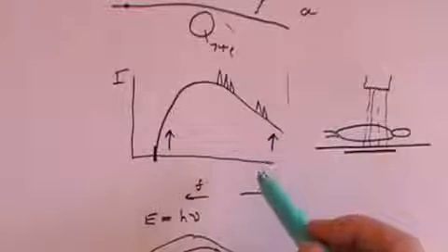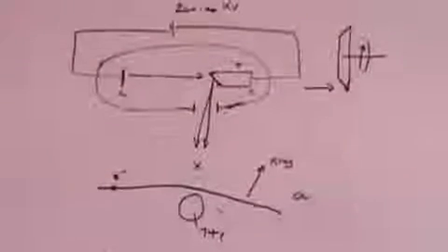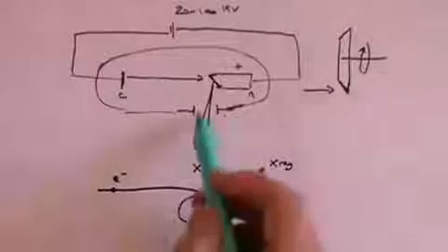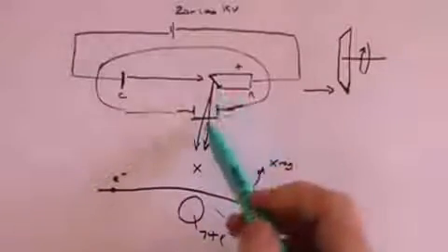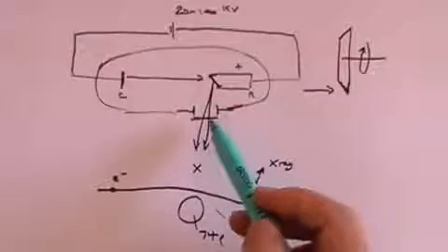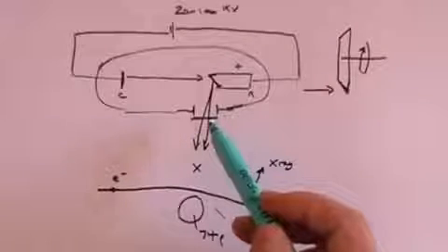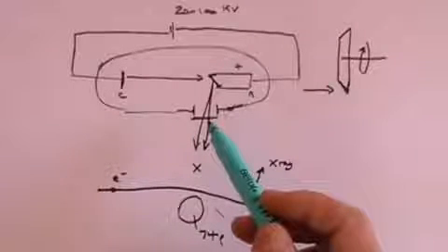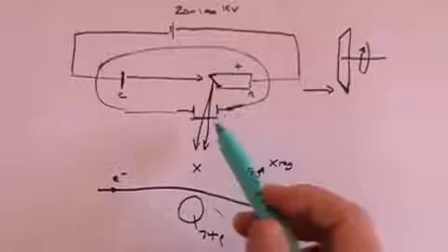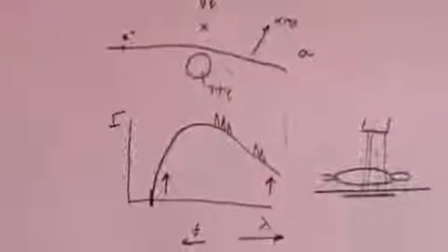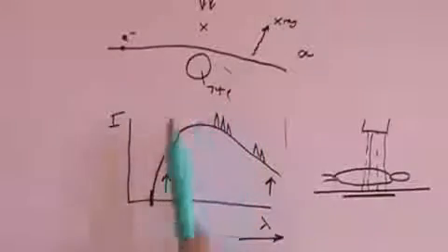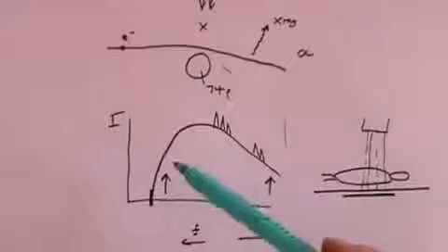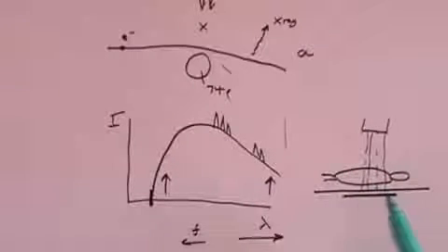And so typically the way that you get rid of those is you put an aluminium plate across the exit of the X-rays, and that aluminium plate will take out all the low energy X-rays that would never penetrate the body, so that you've only now got, as it were, the high end of the X-ray spectrum, and that has got the energy to penetrate and hit the photographic plate.